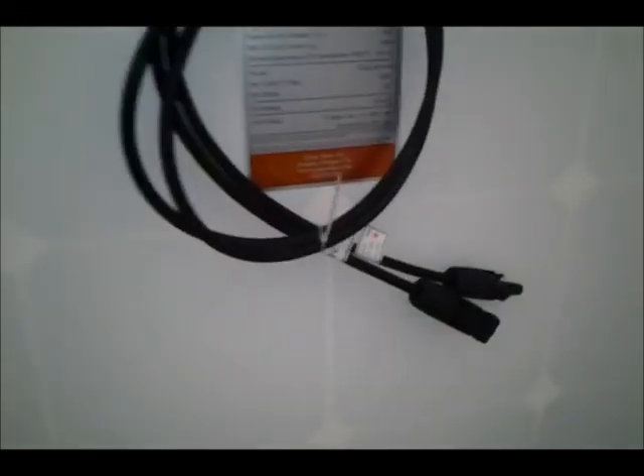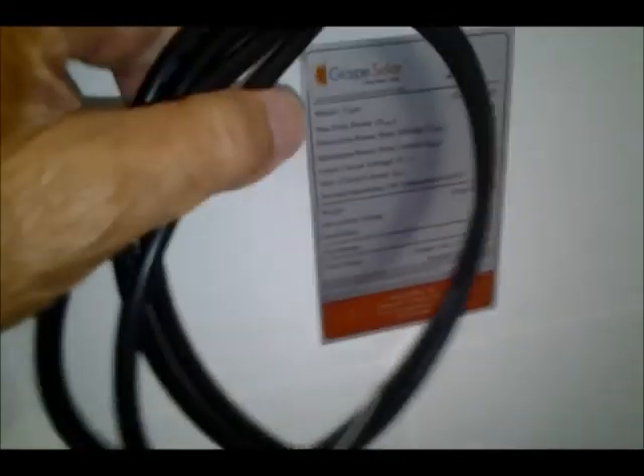On the back you've got your standard MC4 wires, and there's your nameplate: GS-S-265, 265 watts, 31.2 volts. That's the maximum power point current — 8.5 amps. Open circuit voltage is 38 volts. Short circuit current is 9.06 amps. Normal operating cell temperature is 45 plus or minus 2 degrees Celsius. Weight is 20 kilograms, or 44.09 pounds. Maximum system voltage is 600 volts.